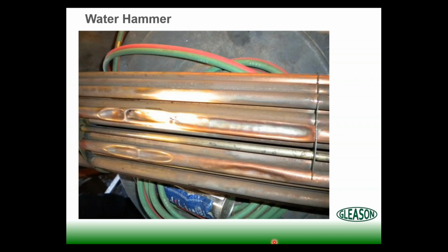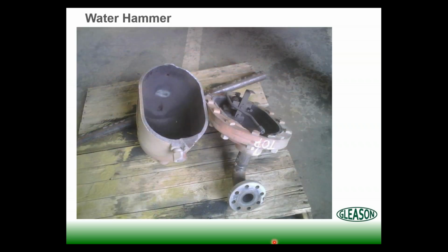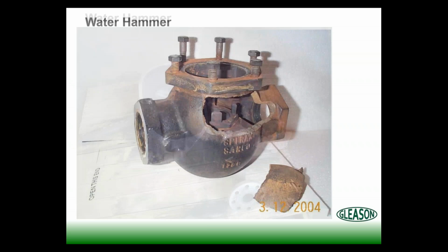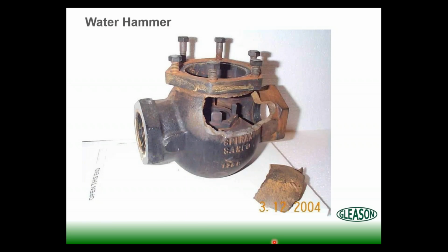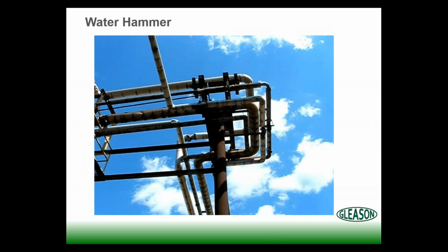Some examples real quick of some water hammer issues. This is a tube bundle that came out of a domestic hot water application. They'd replaced this bundle 3 or 4 times within about a 1-year period, and we'll talk a little bit about how to avoid that. Here's a floating thermostatic style of steam trap. Water hammer did a number on that. Water hammer did some work here on this control valve body.